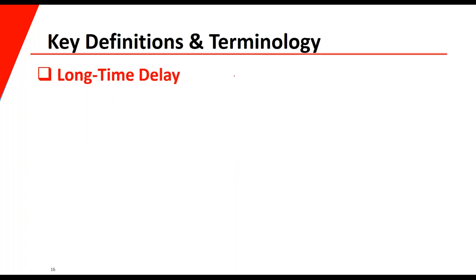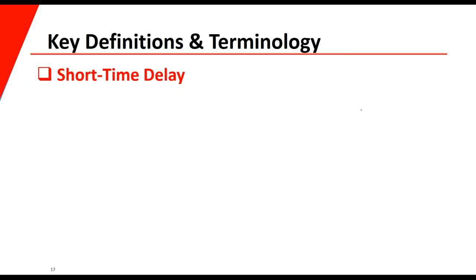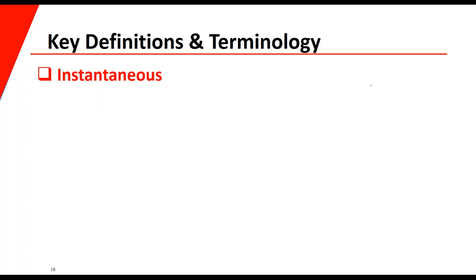Long time delay is one of the features found on a trip device. It provides various settings to protect the circuit from a sustained overload, and will normally take from a few seconds to minutes to trip — or may not trip at all if the overload goes away. Long time delay will have many different settings in most cases to select from, including the pickup value. Short time delay allows the breaker to carry short circuit current for a very brief amount of time, allowing better coordination with downstream protective devices such as molded case breakers or fuses.